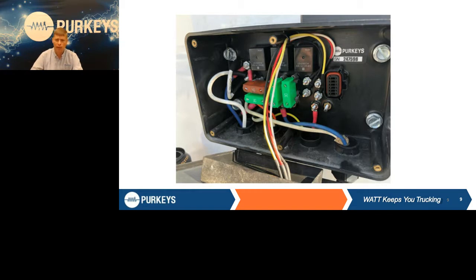Out of sequence from everything we're talking about, but on this one, the reason it wasn't charging properly is somebody had worked on it and moved the orange wire. It should be on the bottom right stud, but they moved it up to another post. Quote unquote, they made the system work, but it didn't work anywhere near like it was supposed to. I'm really surprised it didn't have a thermal incident because of the way they had it wired here and in the battery box.